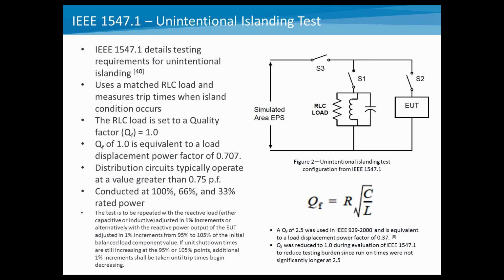system. So basically what this does is it sets up what's called a resonant tank circuit. That RLC load is very tightly matched. It also has this ability, using the L and C, to create a way to try to hold that frequency steady so that the devices can't necessarily push it around. In older tests, like in 929, we were using a quality factor of 2.5. Based on a lot of testing we did in the early 90s, we came to the conclusion that we were seeing very similar results using a quality factor of 1, and that was much easier to actually set up and run that particular test. So that's why the standard now has a Q of 1.